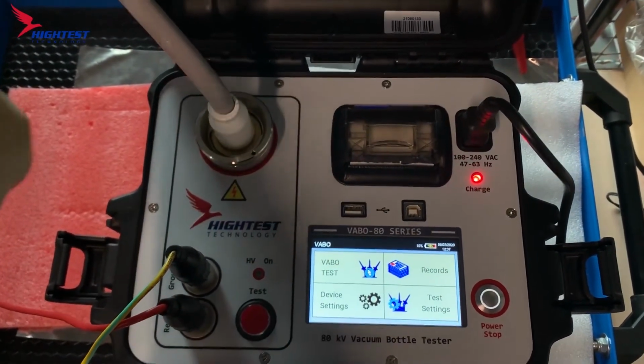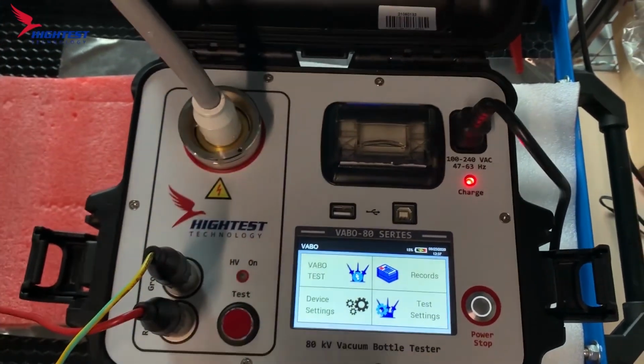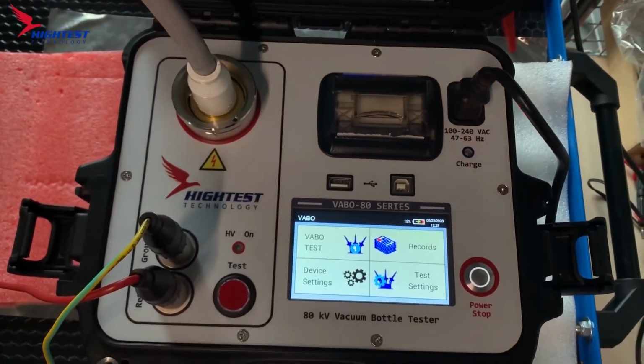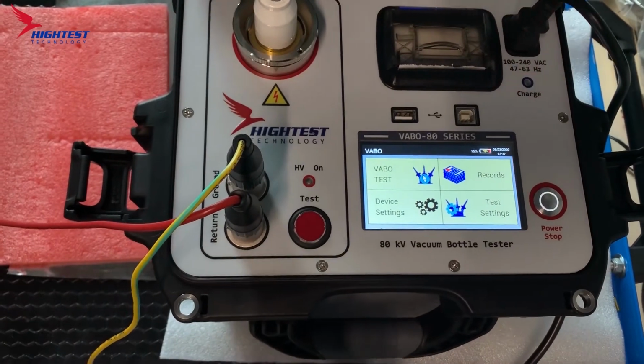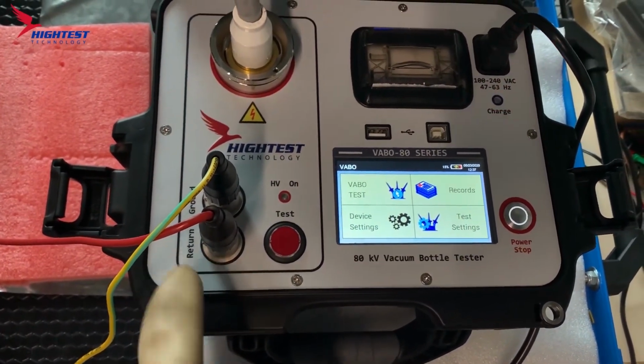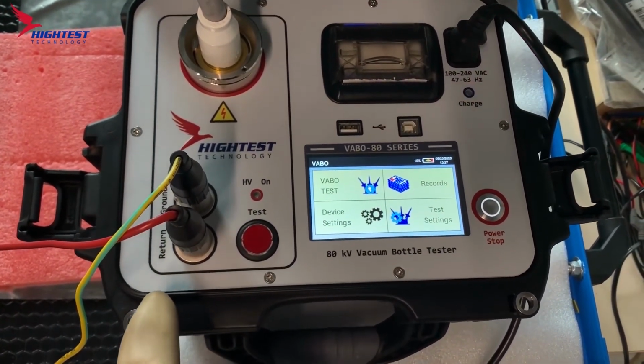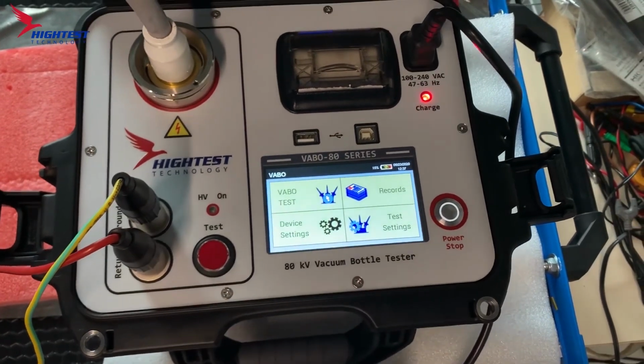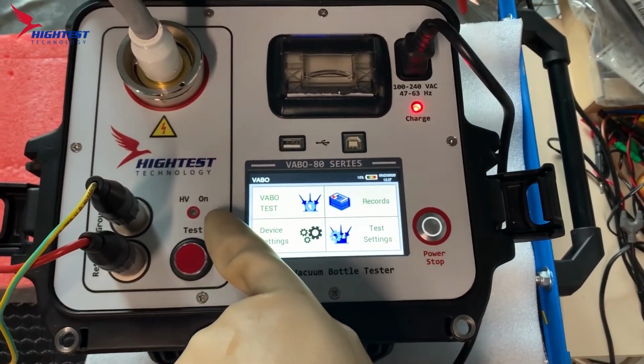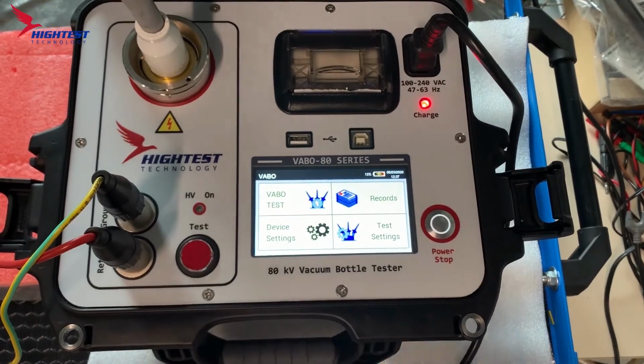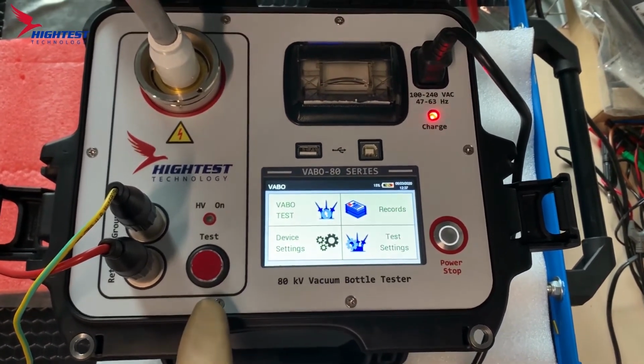a side note, you completely push in before you screw in the cable here. Please remember that. We have our return and ground. Our ground is for extra safety, and our return is so that our high voltage comes back to the device. Our high voltage on indicator to show that it is on and currently testing, and our test button.